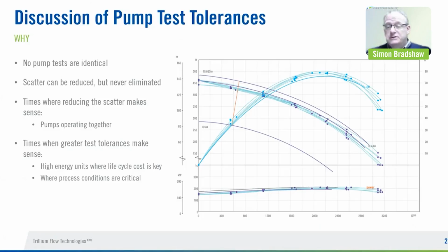There are times when you do want to reduce that scatter. For example, if you have operating pumps in parallel where you need to match the performance very closely, for example, for the reliability of the system. There are other times when it makes less sense, when it's, say, an intermittent pump, and a single fire pump, for example, where you don't really need to worry as much about it. So that's one of the considerations there, where as you prescribe tighter and tighter test tolerances, now the manufacturer has to apply better methods, better controls, and of course all of that costs money, as we've talked about. The graphic just shows a typical pump with a whole bunch of tests against it, and you can see that's pretty much as expected for an average manufacturer, the kind of scatter that you would get, just to set the stage. Next slide.